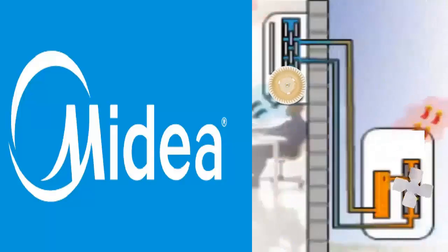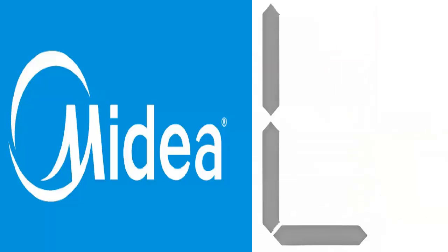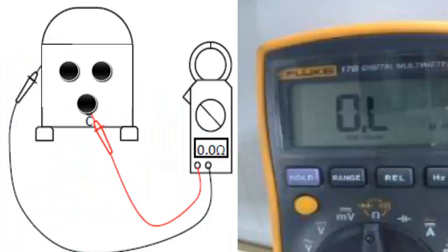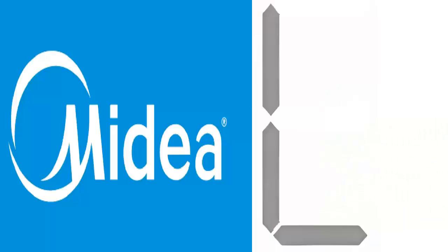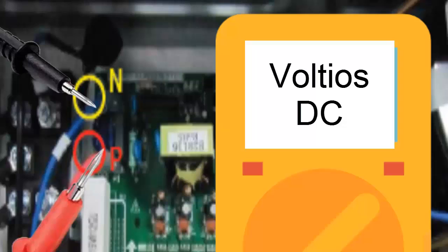2. Measure the electrical resistance between each terminal or pin and the compressor casing or ground. The value obtained should tend towards infinity. 3. Perform a module check by measuring the DC voltage between the terminals identified as P and N. The value obtained should be approximately 1.41 times the supply voltage from the electrical grid.